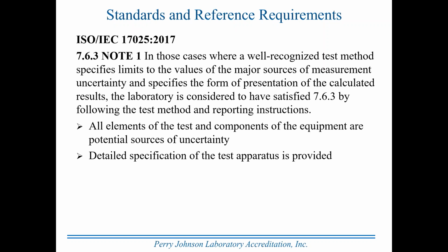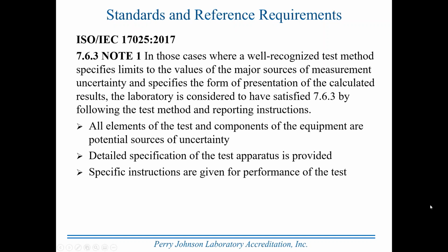But the test apparatus is well defined. Now, the small unit by unit variation that occurs in manufacture is one of the contributors to uncertainty of measurement with these pieces of equipment. Specific instructions are given for performance of the test. In other words, the manner in which the test is performed is detailed by specific step-by-step instructions, and the expectation is that those instructions will be followed as published every time a test is performed.